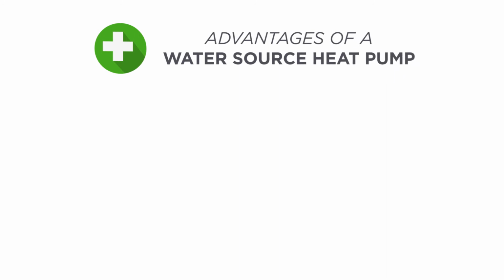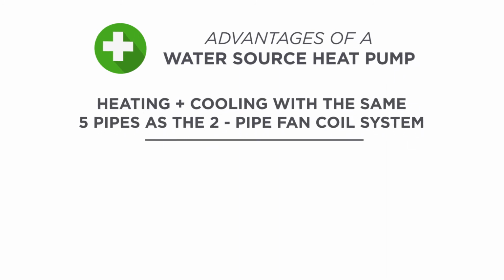The advantage here? A water source heat pump allows the tenant to have heating and cooling with the same 5 pipes as a 2-pipe fan coil system, because the heat pump can provide cold water for cooling, and if someone needs heat, they can have heat off of the hot water rejected from the compressor heat. Using 5 pipes keeps the piping and installation costs at the same level as a 2-pipe fan coil system.